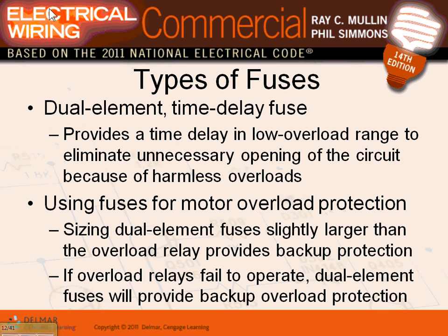Fuses, dual element time delay fuses. Fuses, guys, they call them fast acting fuse, or dual element time delay fuse, or current limiting fuse. The dual element time delay fuse says dual because there are two elements in it, one for overload and one for short circuit. That's the whole time delay. It allows you a little bit of time to start the motors.